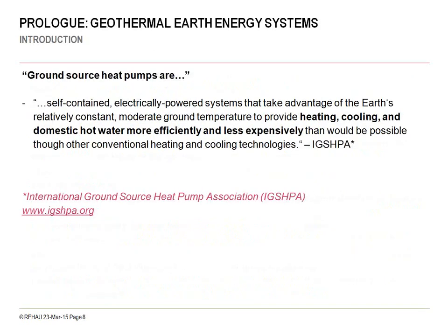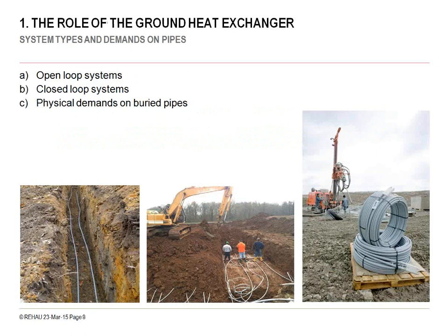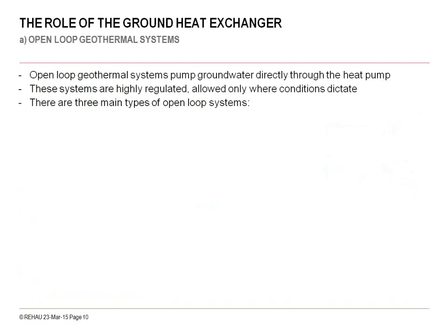So, geothermal earth energy systems. This is a blurb from the International Ground Source Heat Pump Association. Ground source heat pumps are all electrically powered units that utilize the relatively constant temperature of the earth for heating and cooling and generation of domestic hot water. These are considered to be some of the most energy efficient systems compared to conventional heating and cooling technologies. The two types of geothermal fields are open loop and closed loop. We'll talk a little bit more about that, and then we'll be talking about some of the physical demands that are placed on these piping systems.